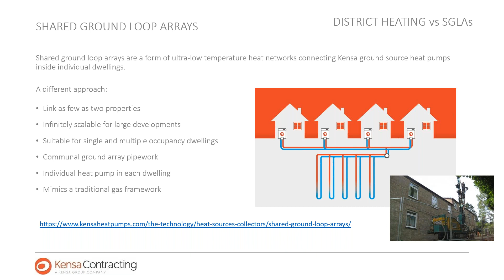And if you go on to Kensa Contracting, you'll see more detail of that down in the southwest. It's suitable for single and multiple occupancy dwellings, that is houses and apartments. It's a communal ground array pipework, and it mimics a traditional gas framework. So that diagram you see on the right-hand side shows our boreholes, which typically connect to a manifold, which will then feed each individual property and its own individual heat pump to supply the heating and hot water.